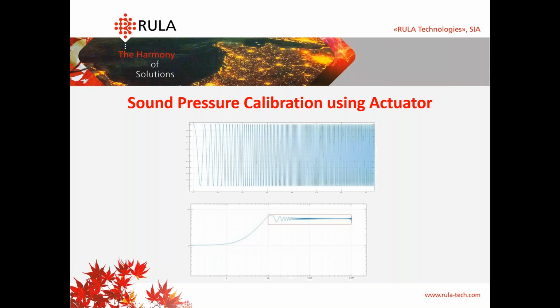Excellent. And here, let's talk a little bit more about the logarithmic sine chirp. You see this signal here, and here's the spectrum of this signal. This way, we can speed up the calibration. We use our actuator, and instead of generating a single frequency, we generate the sine chirp, for example 8 or 10 times, and get the spectrum. After that, we correct its average and get our results. The precision is really close to the values captured in a more traditional way, but we can save our time. So this calibration may take, for example, 5 minutes.